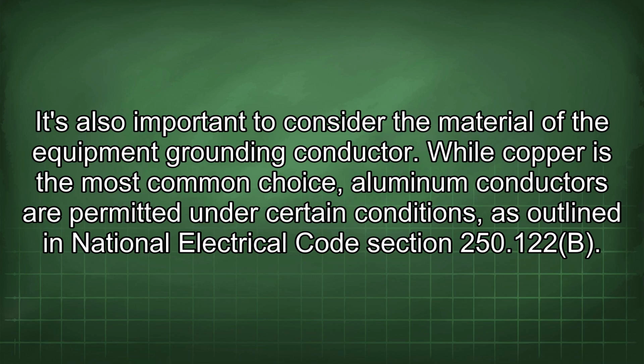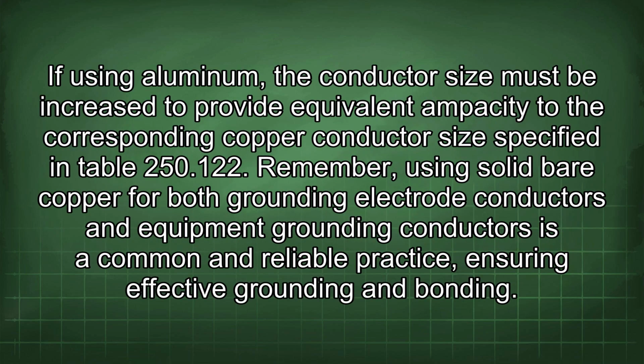It's also important to consider the material of the equipment grounding conductor. While copper is the most common choice, aluminum conductors are permitted under certain conditions, as outlined in National Electrical Code Section 250.122(B). If using aluminum, the conductor size must be increased to provide equivalent ampacity to the corresponding copper conductor size specified in Table 250.122. Remember, using solid bare copper for both grounding electrode conductors and equipment grounding conductors is a common and reliable practice, ensuring effective grounding and bonding.